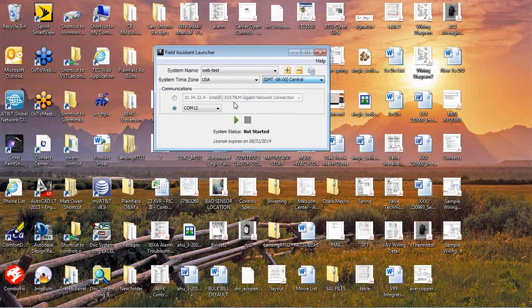So the next thing to look at would be these communication radio buttons. This communication radio button would be if you're trying to communicate through the Ethernet connection, which is something that we do not offer with our Field Assistant. I think it's only available for future connection here. So you would always want to make sure you check this box which says COM, and then it'll give you a port. Now this is referring to the USB port that you actually plug this USB converter into.